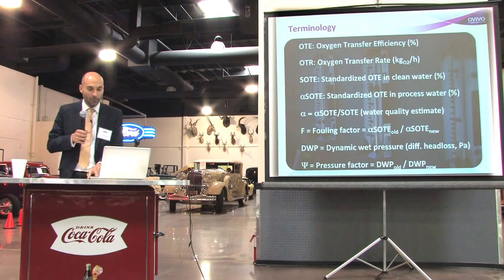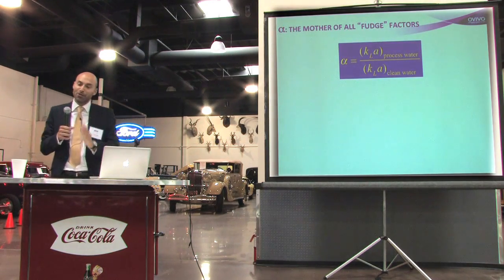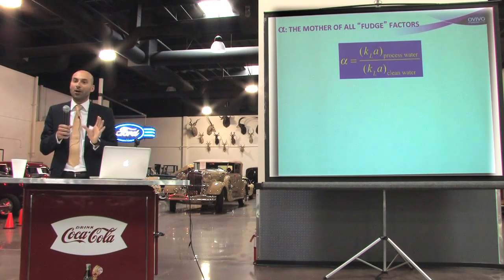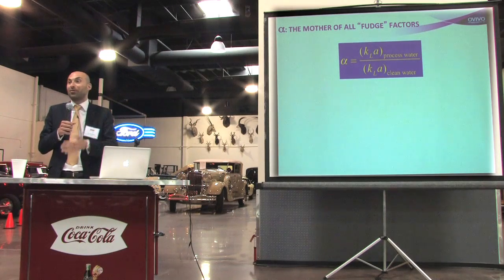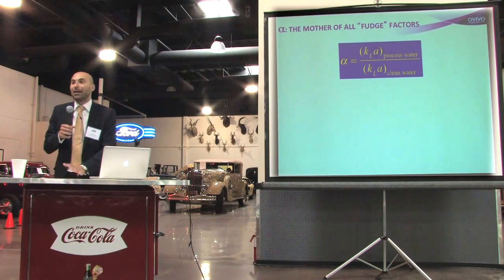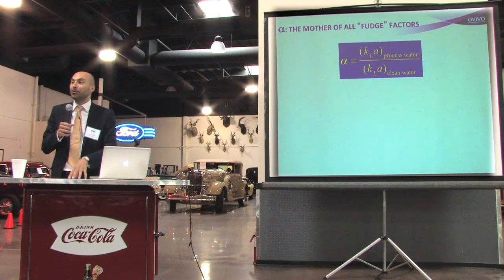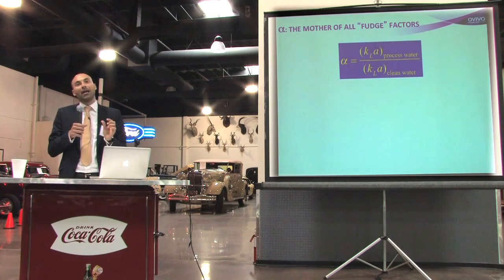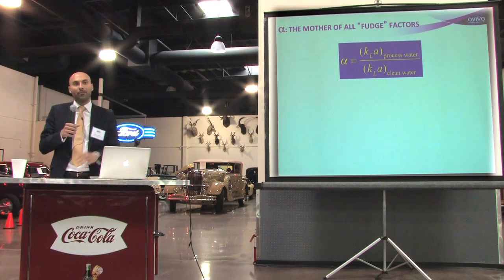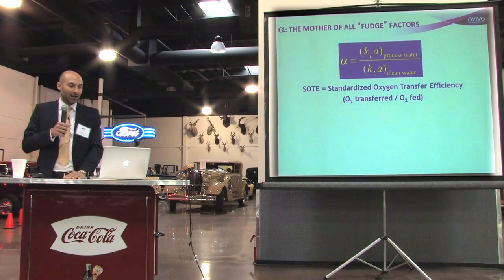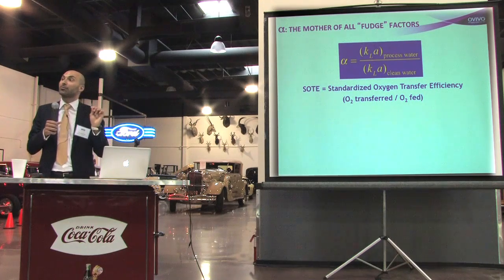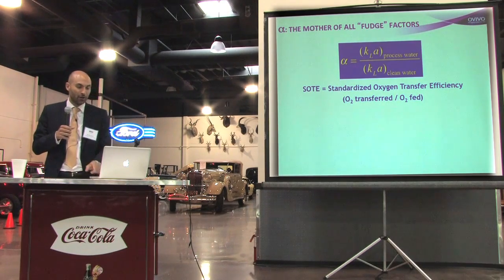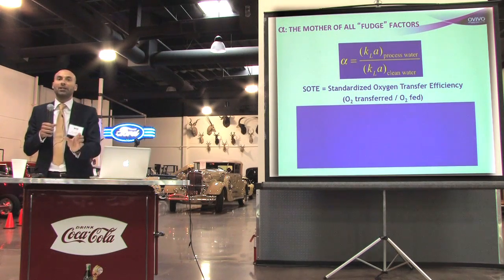Alpha is the mother of all fudge factors — it includes everything we don't understand about wastewater, because we cannot know beforehand what's in it. Alpha is the scaling factor representing the difference between the oxygen transfer coefficient KLA in clean water versus process water. The manufacturer provides the SOTE clean water value — so many percent per foot of depth — and your operating efficiency at any given time is the product of SOTE and alpha.